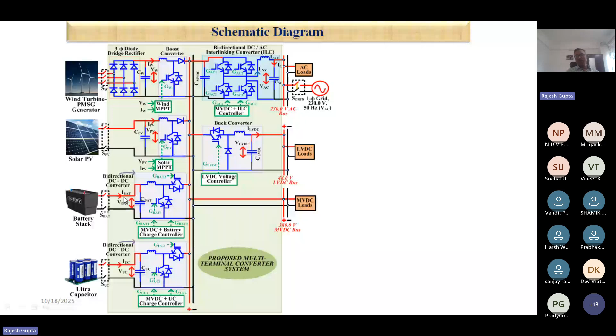This storage is connected through a bidirectional DC-DC converter, with a battery stack and an ultra capacitor. We put a super capacitor in the DC bus for temporary support, especially during transient periods, and regular batteries to support the MVDC bus in case there's no solar, no wind, or both unavailable, or during blackout, when batteries are of much use. This is how we worked on this system.